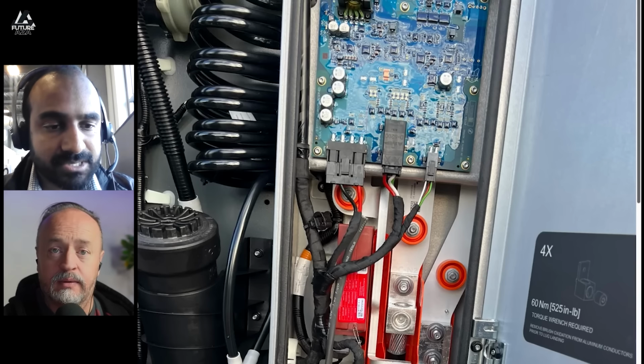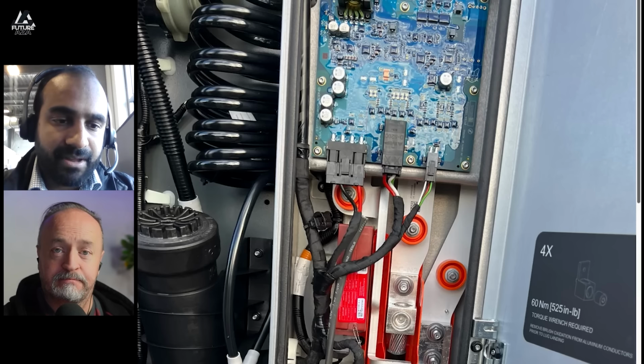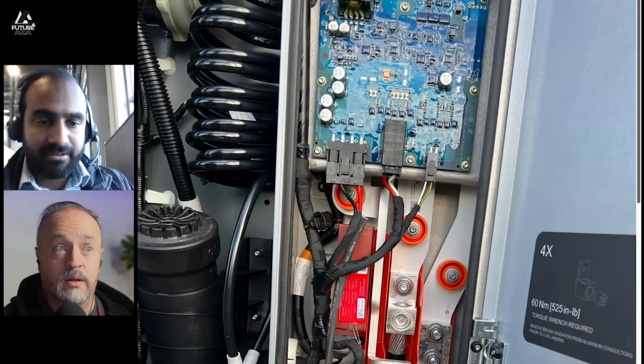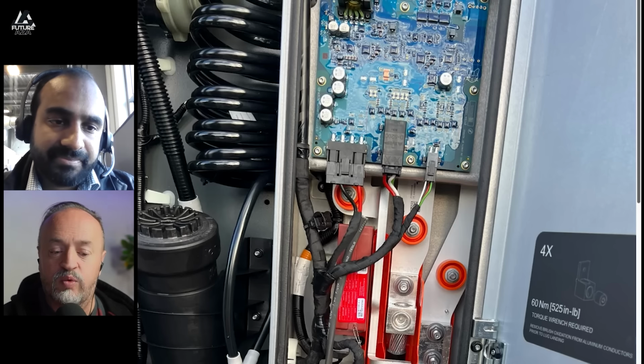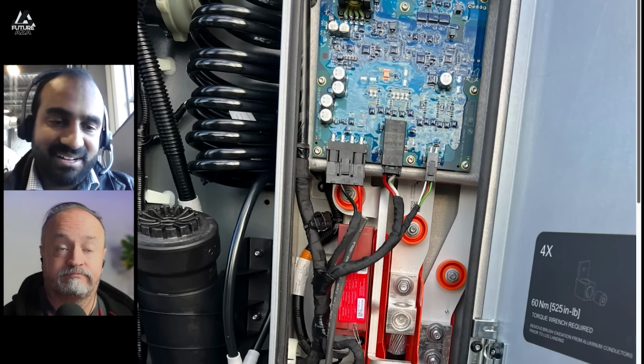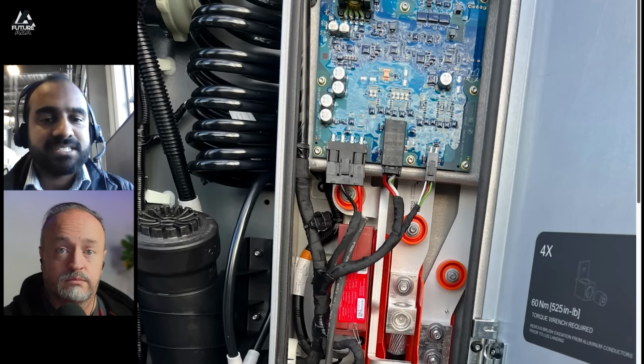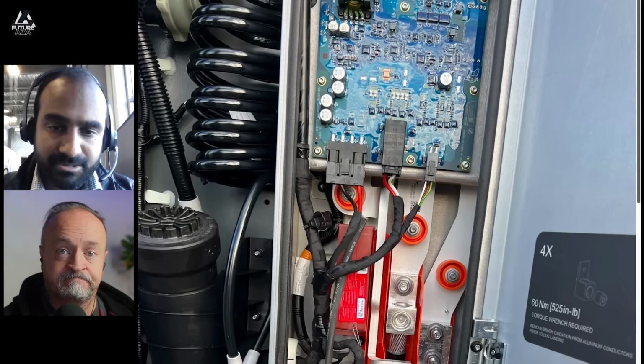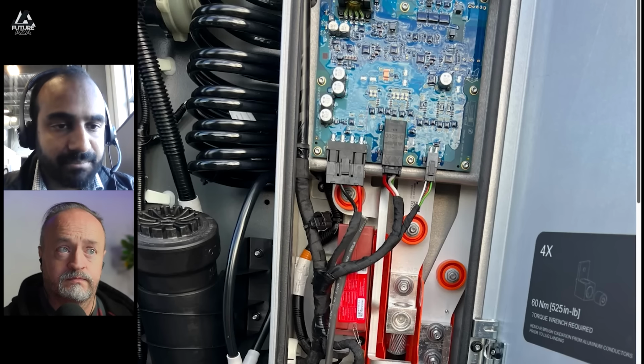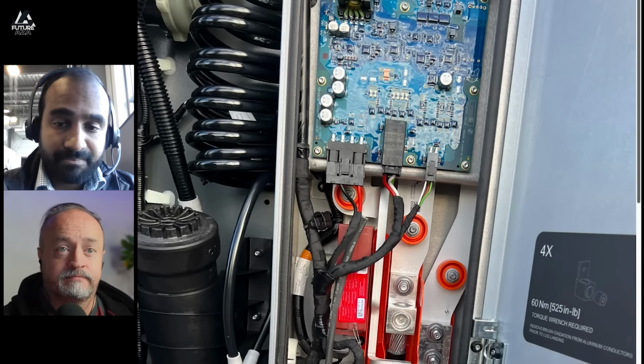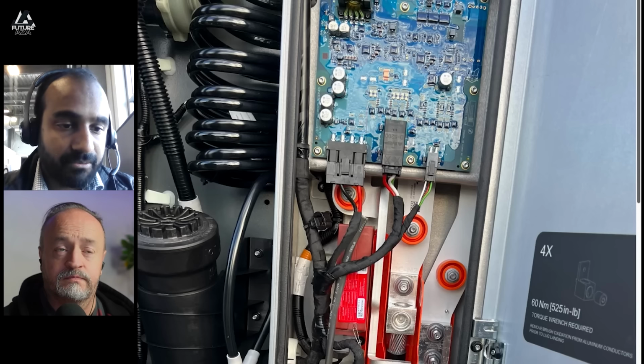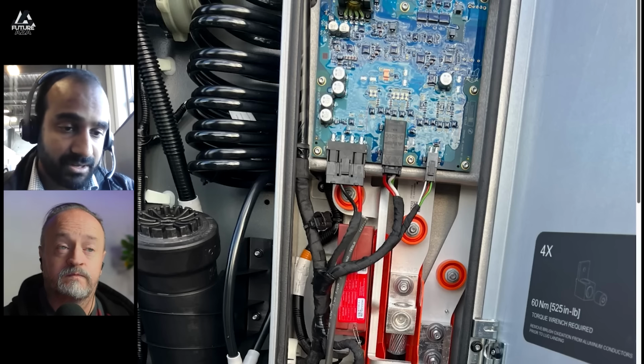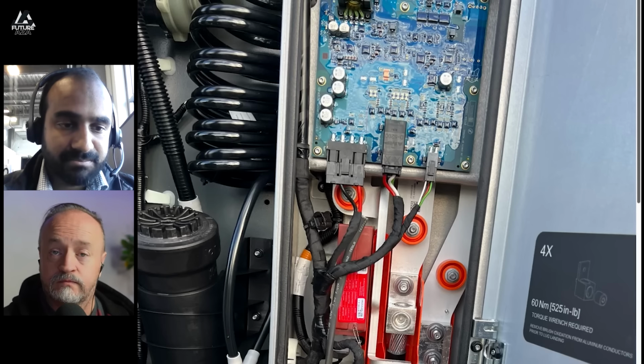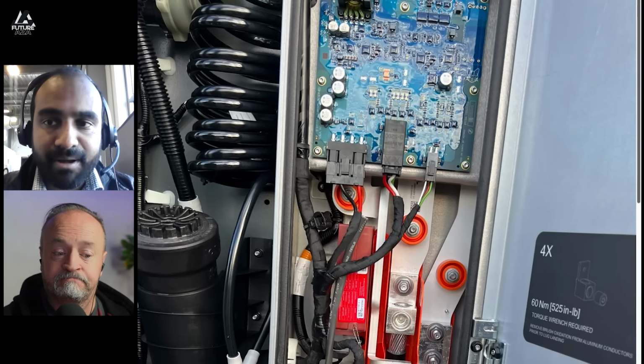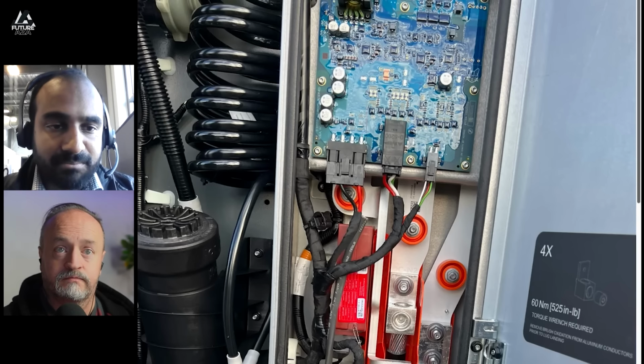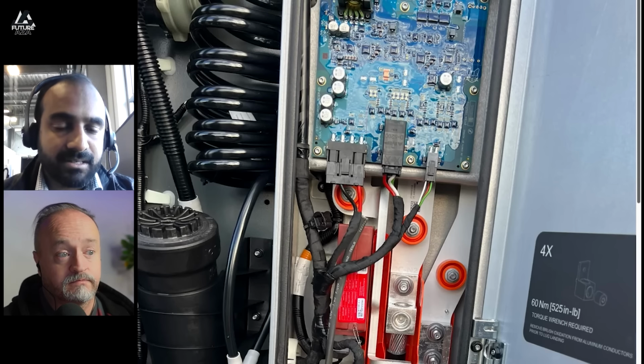It's a very common thing people do to PCBs to prevent water and humidity from slowly creeping in and corroding them. Do you have a problem with ocean water? Yes, we call that salt fog - it's a standard environmental test for producing many things, including EV charging equipment. It's part of the testing program we have to do, making sure things can survive salt fog, because you don't have that problem in the Arizona desert, but half a mile from the Atlantic coast, that salt fog slowly causes corrosion.